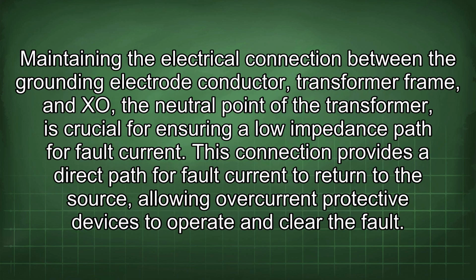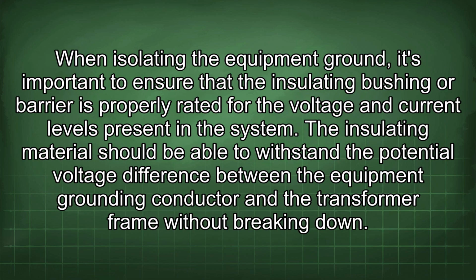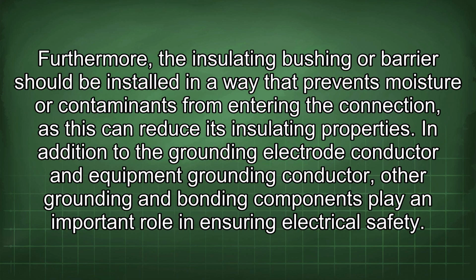Maintaining the electrical connection between the grounding electrode conductor, transformer frame, and the neutral point of the transformer is crucial for ensuring a low impedance path for fault current. This connection provides a direct path for fault current to return to the source, allowing overcurrent protective devices to operate and clear the fault. When isolating the equipment ground, it's important to ensure that the insulating bushing or barrier is properly rated for the voltage and current levels present in the system. The insulating material should be able to withstand the potential voltage difference between the equipment grounding conductor and the transformer frame without breaking down. Furthermore, the insulating bushing or barrier should be installed in a way that prevents moisture or contaminants from entering the connection, as this can reduce its insulating properties.